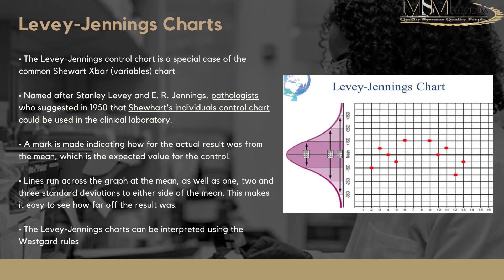Normally, the two standard deviation limit is seen as your warning limit, while the three standard deviation limit is your action limit. With some systems, the one-sigma is the warning and two-sigma is the action limit, meaning anything outside two standard deviations is considered out of control. Levy-Jennings charts are interpreted using Westgard rules, which we'll discuss shortly. You'll also notice that a Levy-Jennings chart is essentially a sideways normal distribution curve.